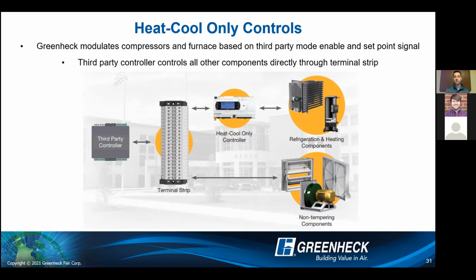If it is non-tempering components like energy wheels, fans, dampers, things like that, there's direct control over that with that third-party controller. Now, if it is things related to refrigeration and heating, we have what is called our heat cool only controller that is essentially taking inputs from that third-party controller and then modulating the cooling and the heating accordingly to basically maintain set point, stay within the compressor envelope, stay within the safety factors, things like that. But with that, we're still accepting inputs from that third-party controller. So it's the third-party controller that is still telling us when to heat, when to cool, when to dehumidify. It's telling us the set point they want for heating or dehumidification or cooling. And then we're taking that information that we get from that terminal strip, and then we're applying that to our logic to make sure that we're operating that cooling and heating accordingly.